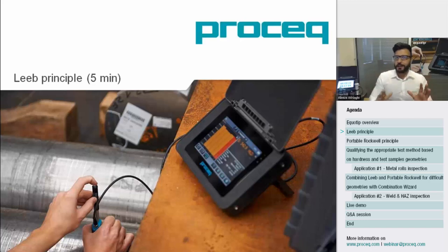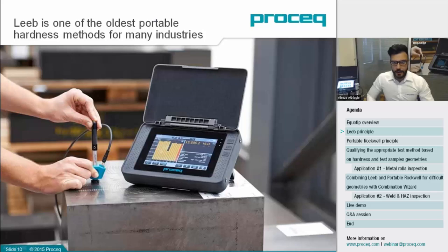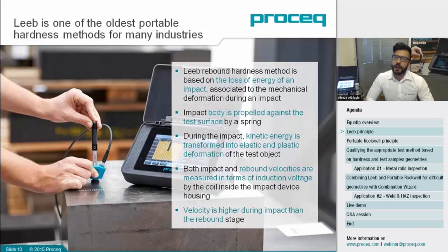That was a brief introduction to the device, because we are going to be working with it today — not only looking at its functionality, but going into the combination wizard in particular. We've got some examples for you that you'll see as we go through the slides. Let's begin with the Leeb Principle, which I believe many of you are already familiar with. Leeb is also referred to as a dynamic hardness testing method. It's portable.